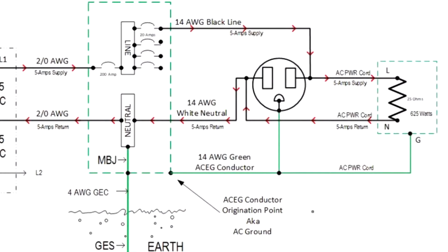Now, some think that ground and neutral are the same thing. This is not true. The neutral, or grounded circuit conductor, carries normal operating line current. The ground does not. It does not carry any current whatsoever. It has 0 current. Another thing you can do to look at your power quality, if you were to look here at the wall socket or at the device, is measure voltage between ground and neutral. You should see a little bit.